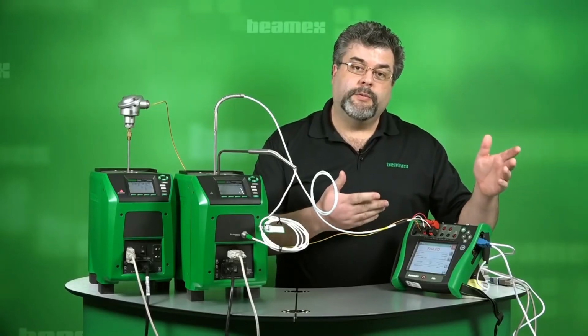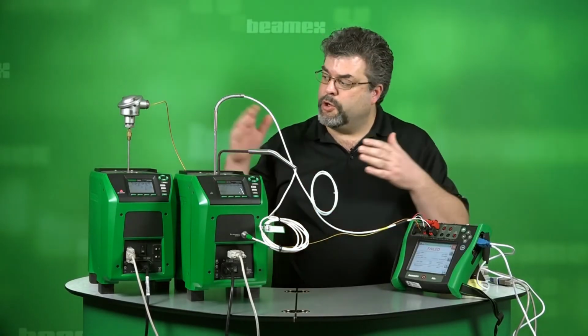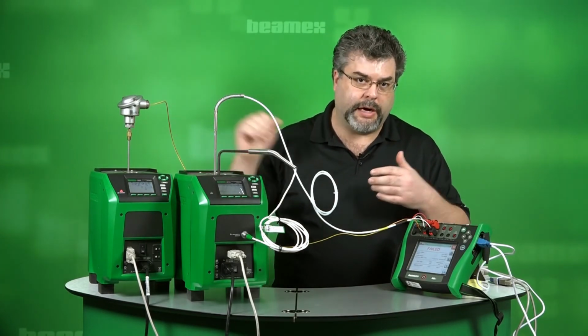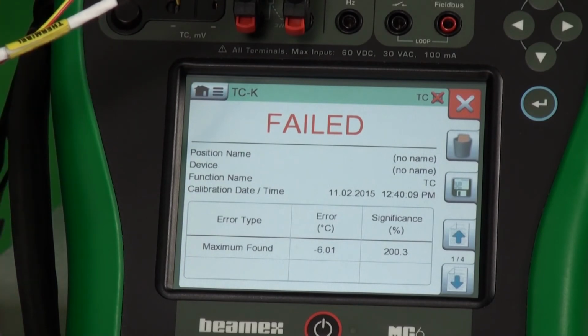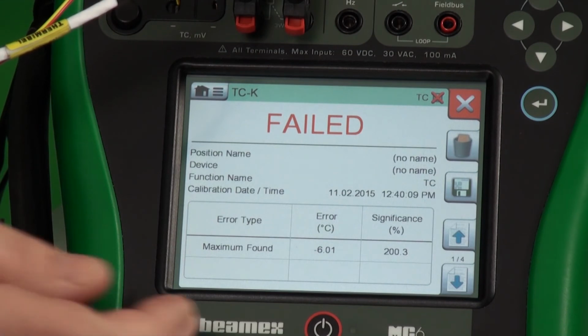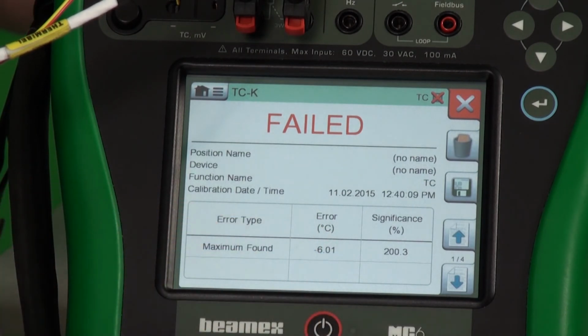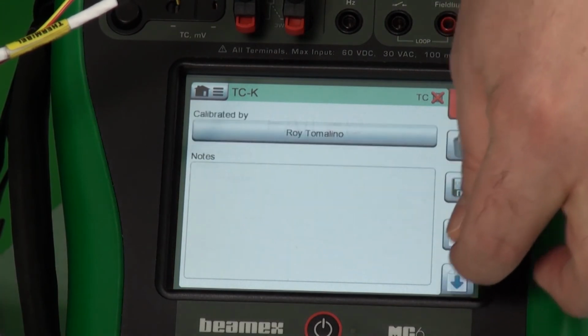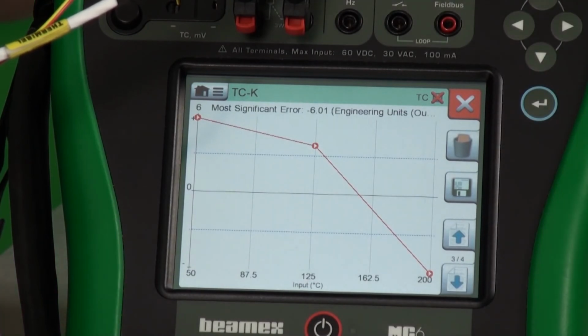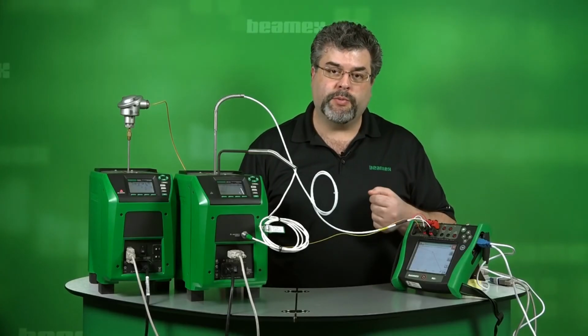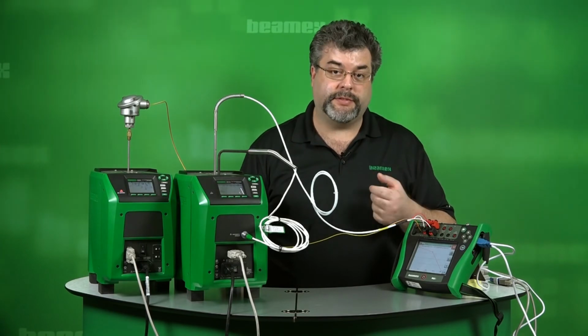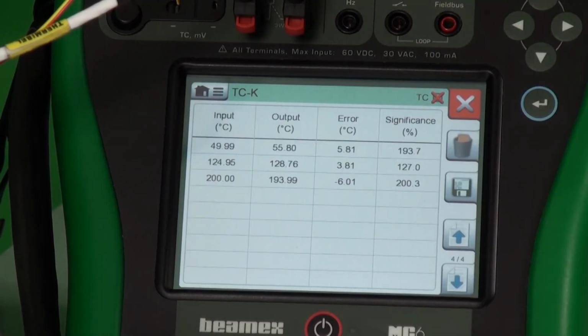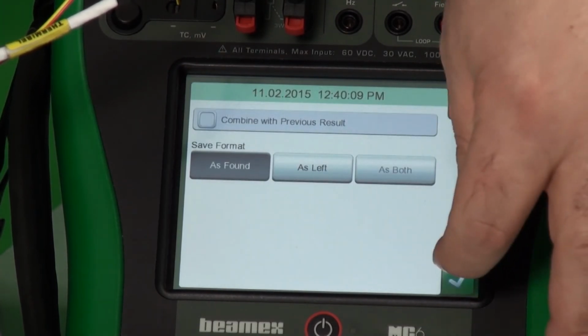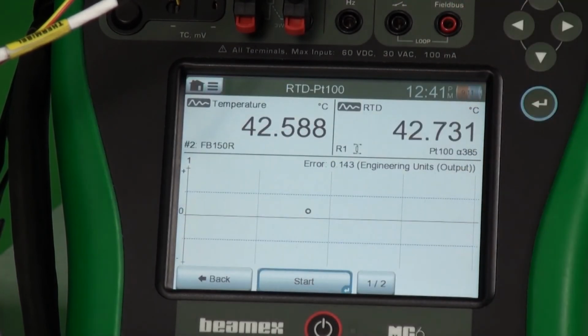Check. Now, we have the test for our thermocouple. Notice it says it right across the top, so now we know we're dealing with the thermocouple from the second temperature block. Now this, well, did it pass or did it fail? It's obvious. It says red failed right across the top, and we get an error here of 6 degrees, so that's well outside of our limit. If we look at the graph, we notice that it was high on the low side, and then it was low on the high side. So thermocouples can't be adjusted, so this needs to be replaced. And this is part of the reason that we calibrate. Things drift. We'll save this as found as well. It's an as found failed, and now it's complete.